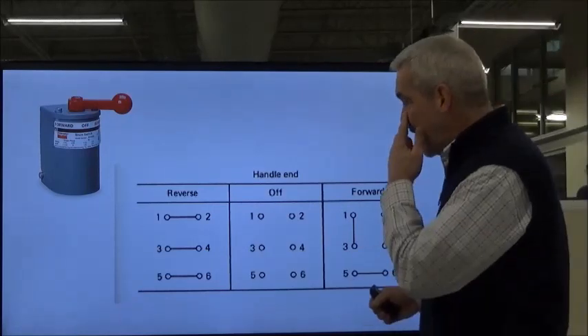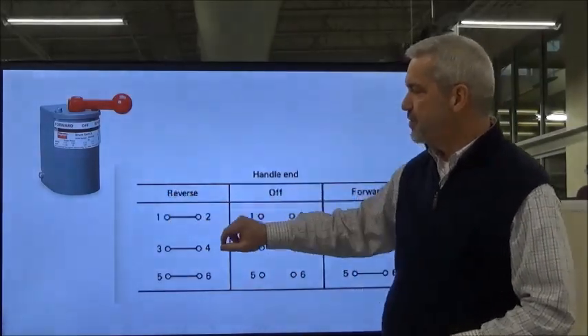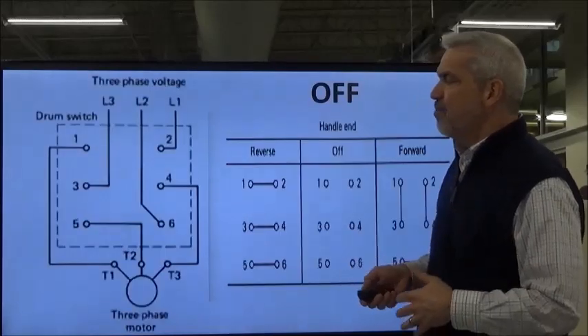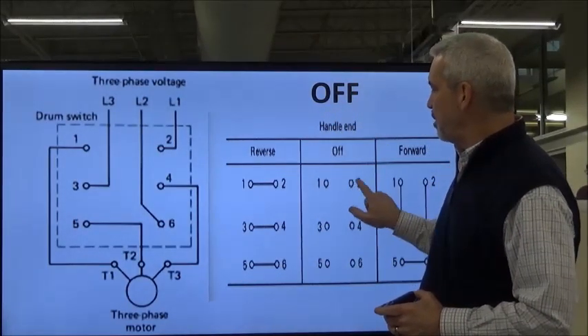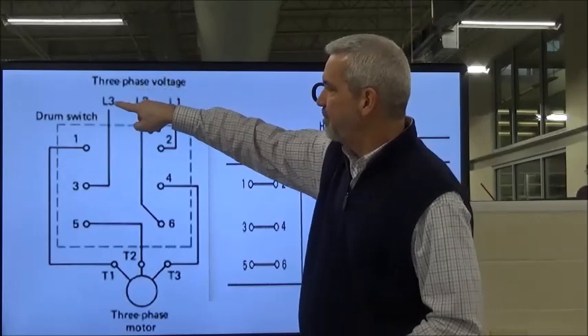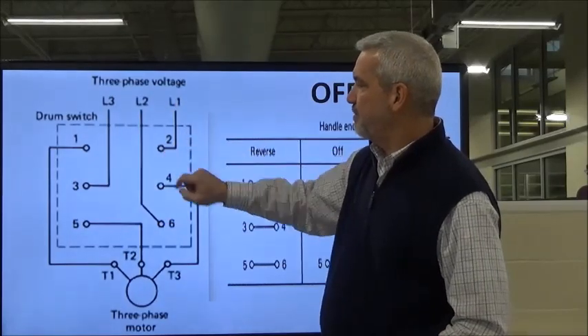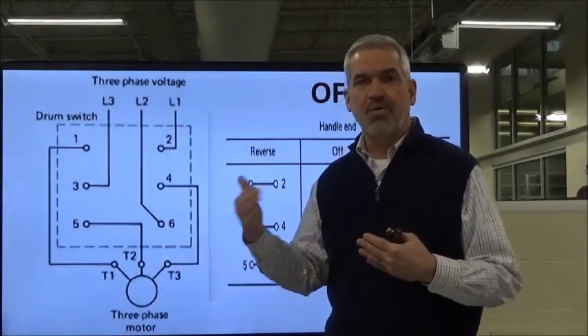When we're in the middle off position, there's no connections whatsoever. When we go to reverse, we're connecting terminals one and two, three and four, and five and six. In the forward direction, we're connecting one and three, two and four, and five and six. Looking at the line voltage connections: line three comes in and lands on terminal one, line two connects to terminal six, and line one connects to terminal two. With no connection made, we've got three phases of voltage sitting there waiting for us to turn it to forward or reverse.